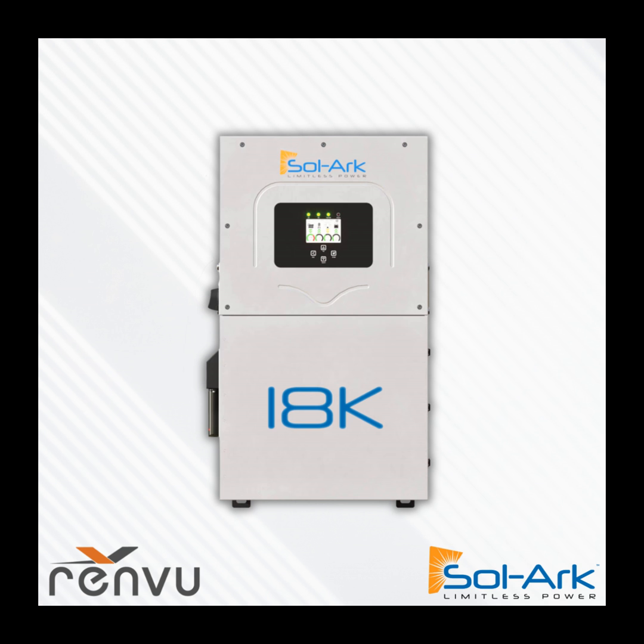If you're looking at the pricing of the AES 210 and want to use it for 208 volt as well, you'll have to put a transformer on both sides of the 60K to go from 480 to 208, and you'll also have to spec out the AccuPanel or AccuEnergy external metering system for that to work when running the 480 volt inverter on a 208 volt application. So maybe you do that for 208 volt, or maybe you don't and just stick to our existing 208 volt battery line, because it's easy, simple, and available.